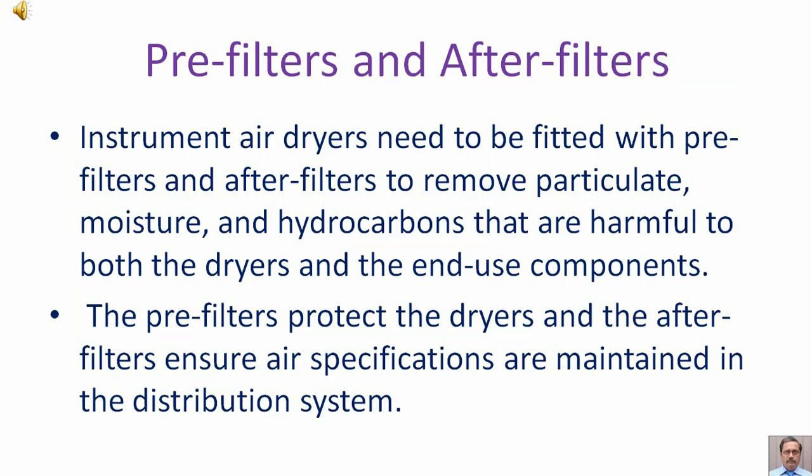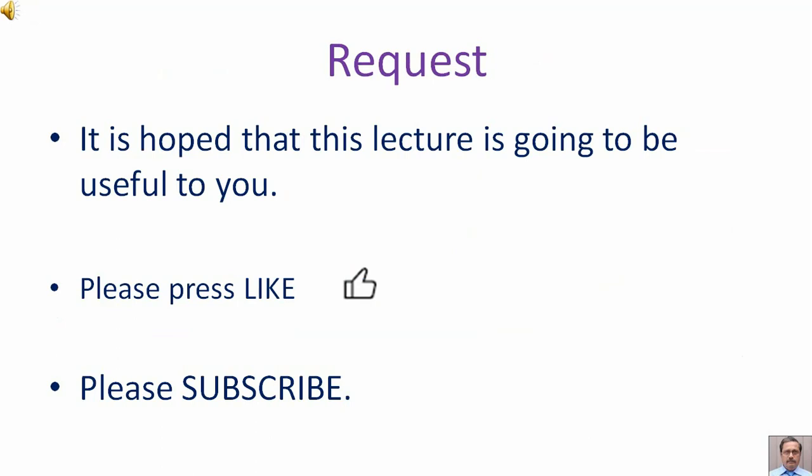Pre-filters and after-filters: instrument air dryers need to be fitted with pre-filters and after-filters to remove particulate, moisture, and hydrocarbons that are harmful to both the dryers and the end-use components. The pre-filter protects the dryers, and the after-filters ensure air specifications are maintained in the distribution system.